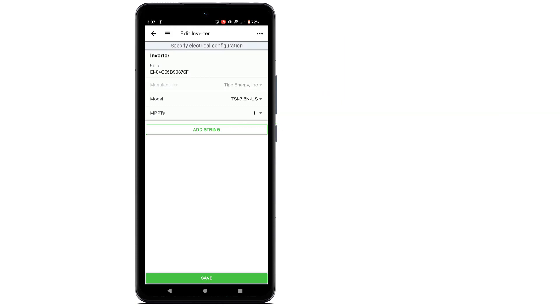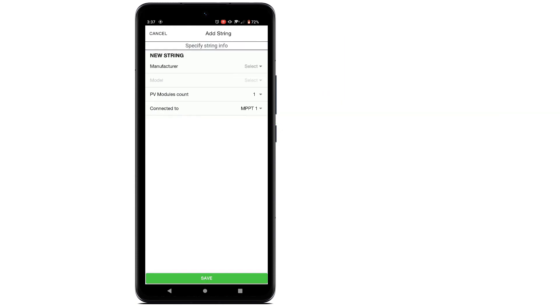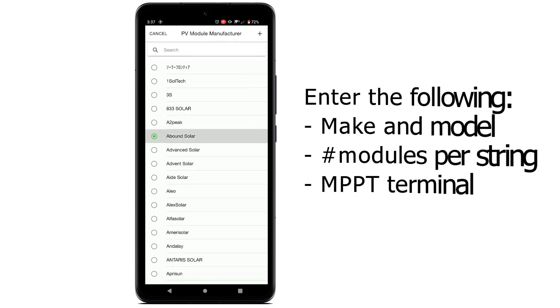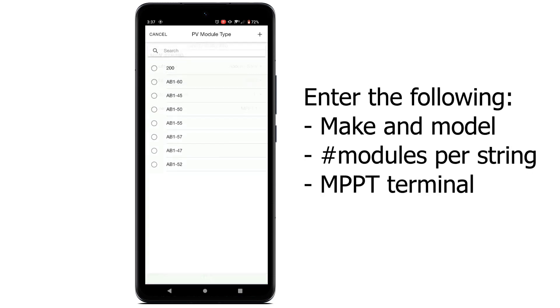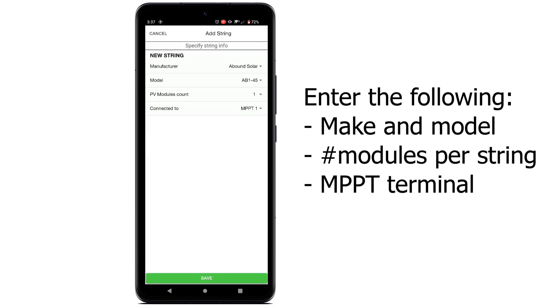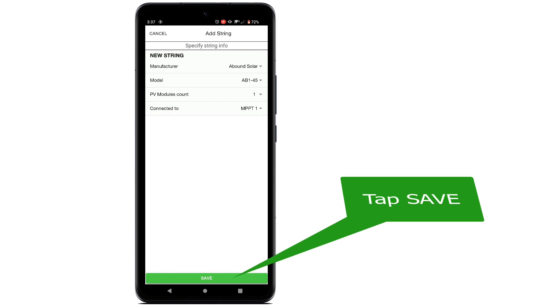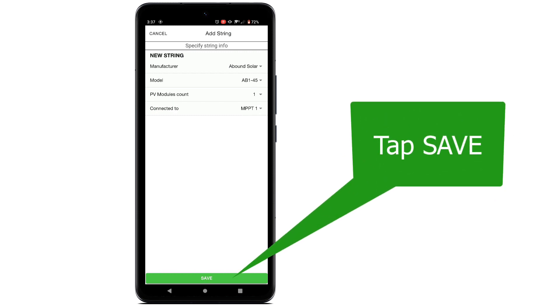Tap Edit to begin entering PV module information. You will enter this data for each string connected to the EI inverter. Enter the make and model of the PV modules, the number of modules on each string, and each MPPT terminal in the EI inverter the string is connected to. Tap Save when complete.